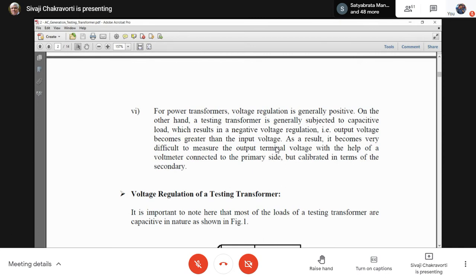Now, when I am applying the voltage, the capacitive current is flowing through the transformer impedance, and then there will be a voltage rise from no load to loaded condition. So if I put a voltmeter and measure the voltage before connecting the equipment, and I see the reading is 28, and then I connect the equipment and apply the same voltage, actually I am making a big mistake, because of the capacitive current there will be a voltage rise, and the terminal voltage could be 30 kV. And that may cause a failure of the equipment under testing. But then it is not a fault of the equipment, it is my fault. It's a failure of the testing engineer.